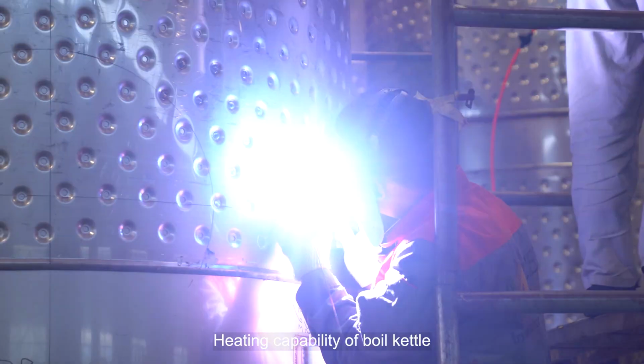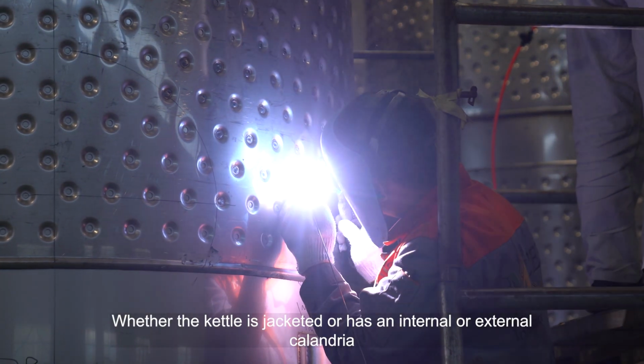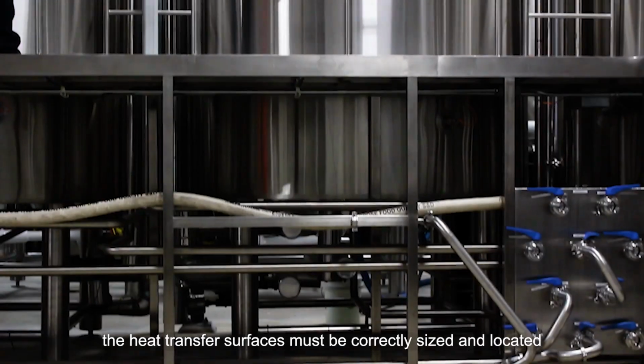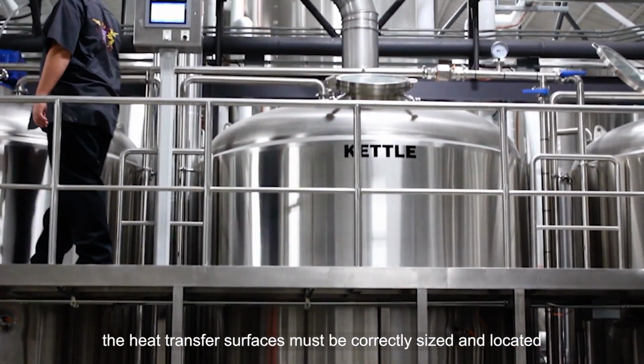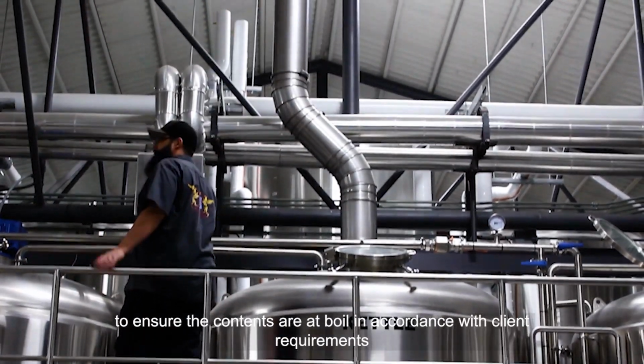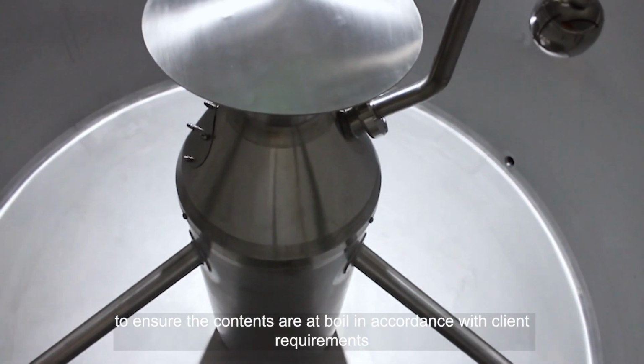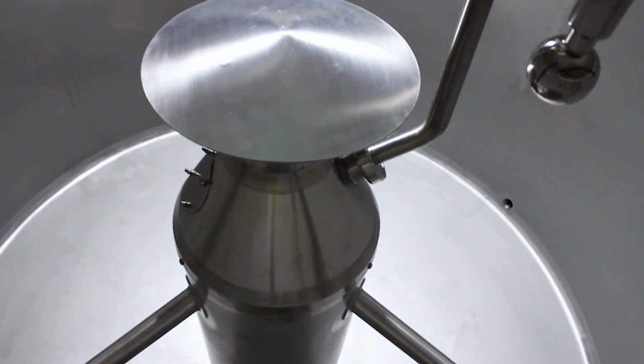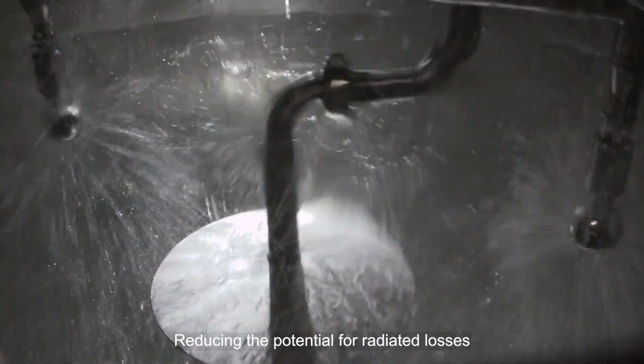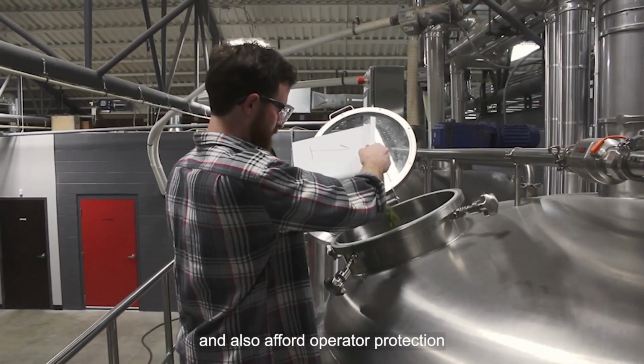Heating capability of boil kettle. Whether the kettle is jacketed or has an internal or external calandria, the heat transfer surfaces must be correctly sized and located to ensure the contents are at boil in accordance with client requirements. Insulation. Reducing the potential for radiated losses and also affording operator protection.